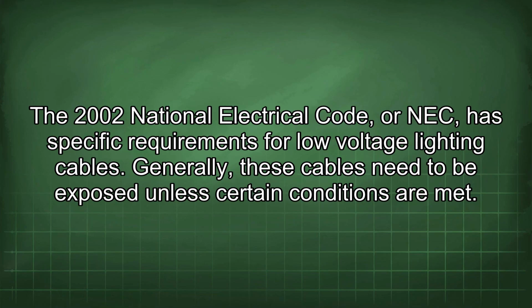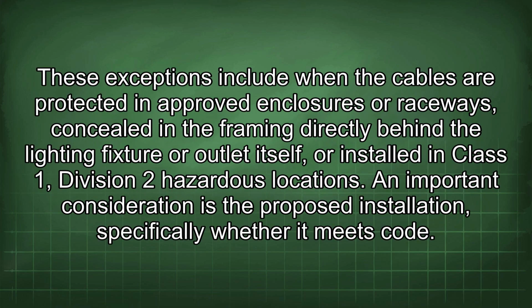The 2002 National Electrical Code, or NEC, has specific requirements for low-voltage lighting cables. Generally, these cables need to be exposed unless certain conditions are met. These exceptions include when the cables are protected in approved enclosures or raceways, concealed in the framing directly behind the lighting fixture or outlet itself, or installed in Class 1, Division 2 hazardous locations. An important consideration is the proposed installation, specifically whether it meets code.